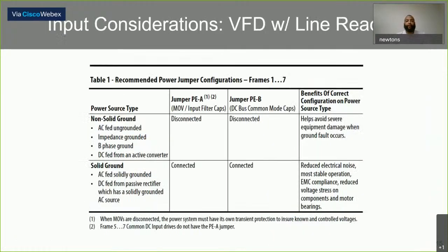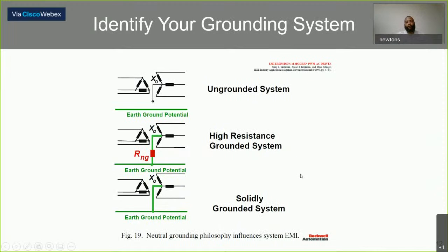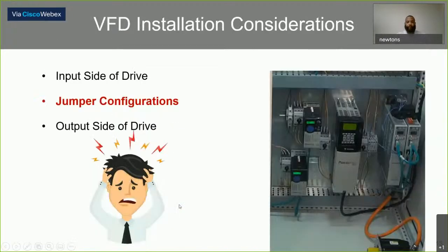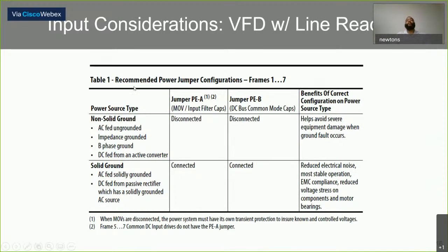So again, to reiterate on the jumper configuration, as we discussed before, on your grounded system, if you have a solidly grounded system, right? If we go back a few slides, if you have a solidly grounded system, three wires coming in, your neutral is grounded to earth. There's no resistor in between it. If you have a PowerFlex 750 drive, there's going to be two power jumpers. Both of them need to be installed. Both of them need to be connected. If you have any other grounded system that's not solidly grounded, they should be disconnected.